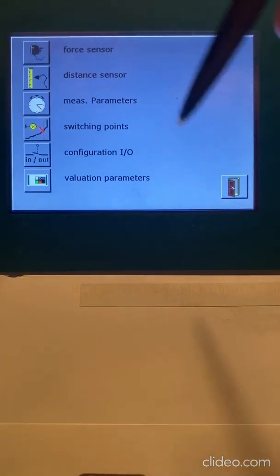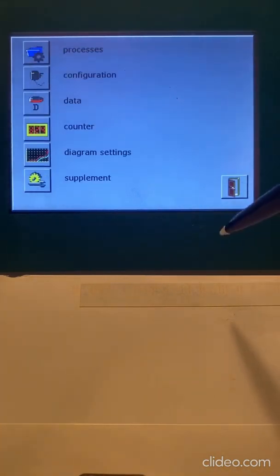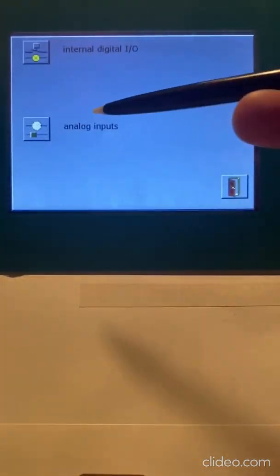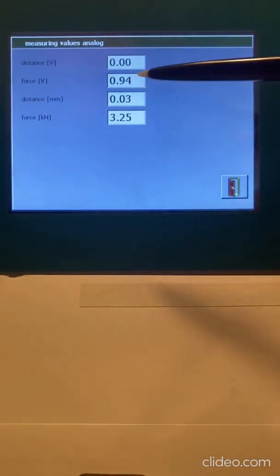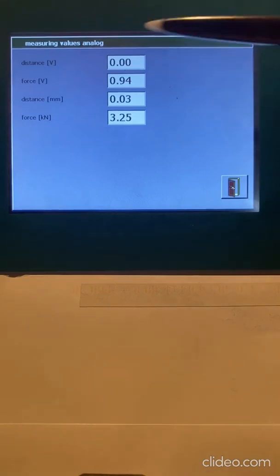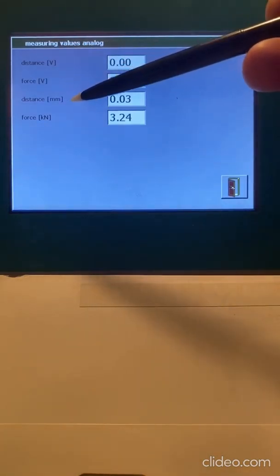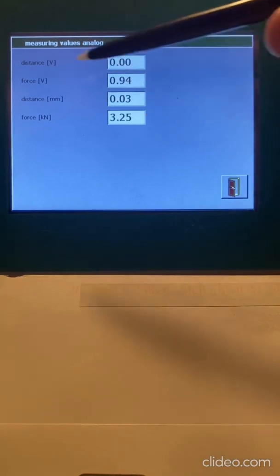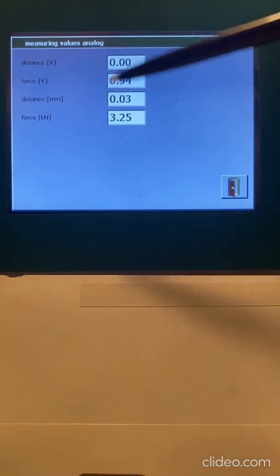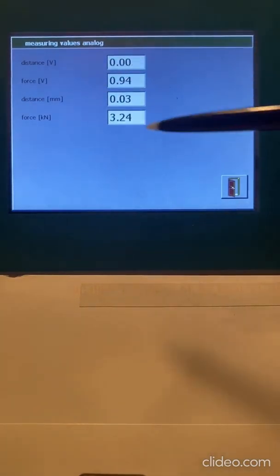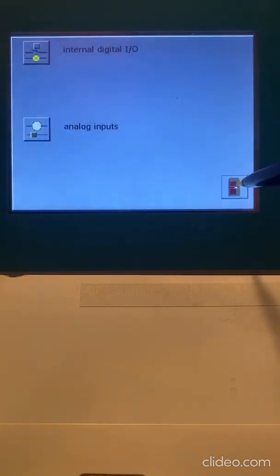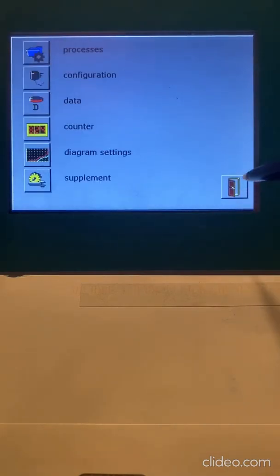And then the other thing I want to do is I'm going to go back to my menu. Once I've set up my sensors, I can go to Supplement, and I can go to I.O. Monitor. And under Supplement and I.O. Monitor, I can physically see the sensors. So here's showing me the voltages of the distance and the force, and this is the actual scaled values. So I've got zero voltage and zero distance. When I drive the press up and down, you're going to be able to see those numbers. This is how you would verify that those sensors are working.